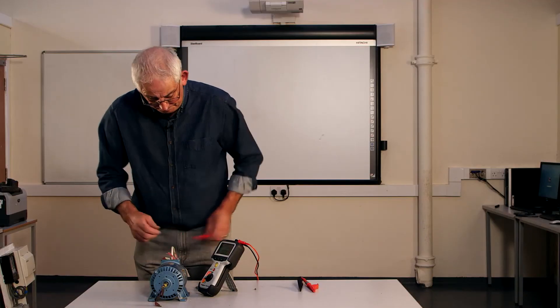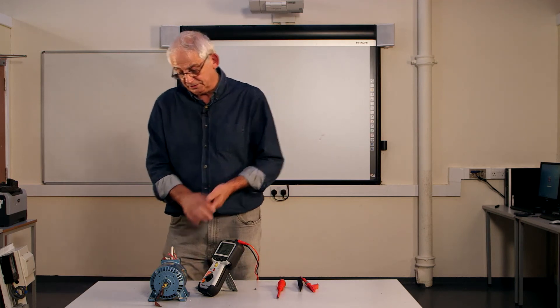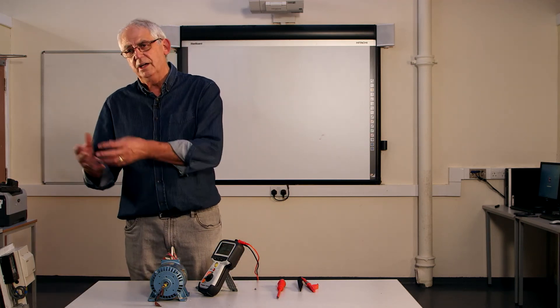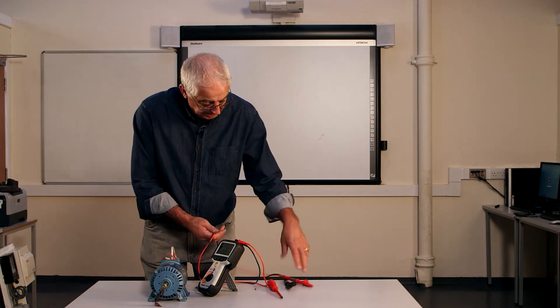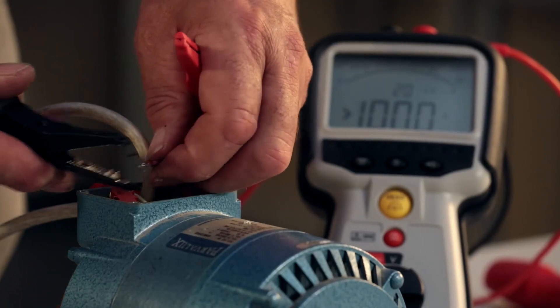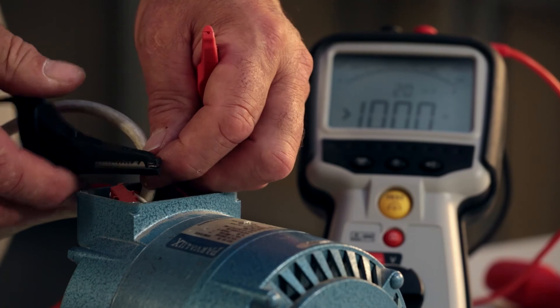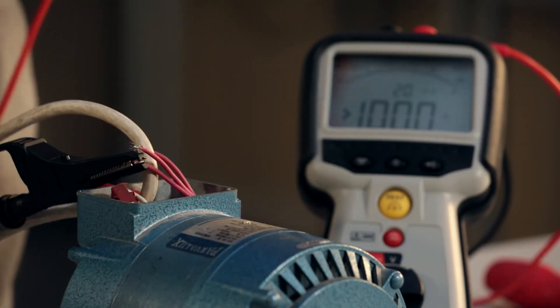Having connected that up, I now need to do an insulation resistance test on the motor to make sure that the windings aren't touching the sides of the motor. So nice easy way of doing that. If I just connect to one of these, it's going to read through all of the windings because of course they're joined together at the other end.